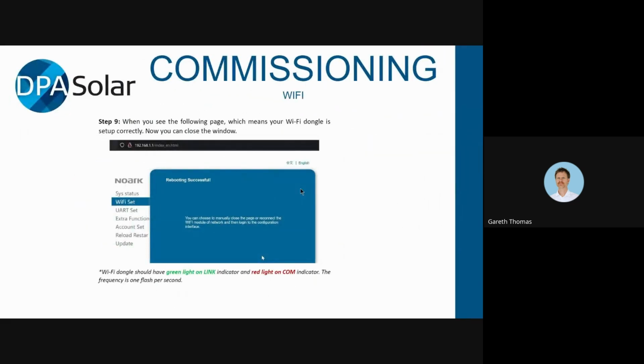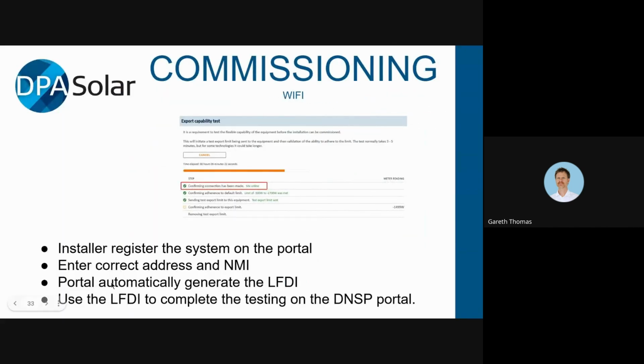After that, you need to go to the Noark portal and you need to create an account if you haven't already created an account. If you're an installer, it's going to need to be an installer account, and you're going to need to register the system by putting in the serial number of the Wi-Fi dongle and of the inverter. Once you've done that, it's going to ask you for the address and the NMI of the customer, and that's going to generate the LFDI, which is needed for the backstop in Victoria. And once you've got that LFDI, you can then go to your DNSP's portal to do the export capability test.